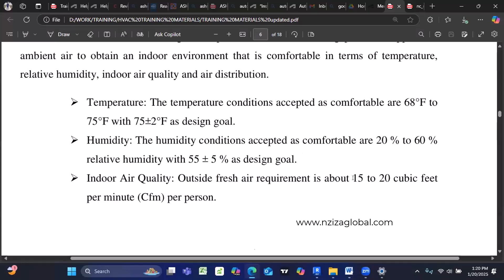For example, a workshop or gym requires its own CFM, meaning air flow. For example, when a person is sitting in the office, not doing any physical activity, they require their own outside air requirement. We'll see. For example, a person in a gym doing a lot of physical activities will require more air. So the requirement is different depending on the building space. We'll see more when we come to designing with ASHRAE.